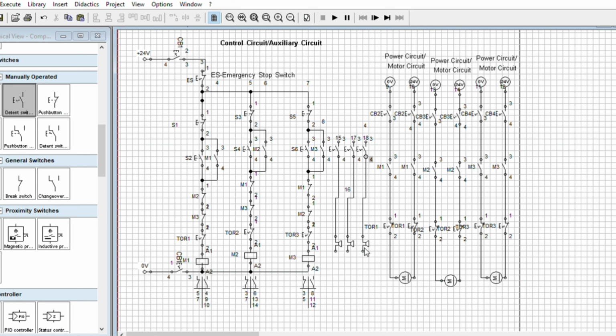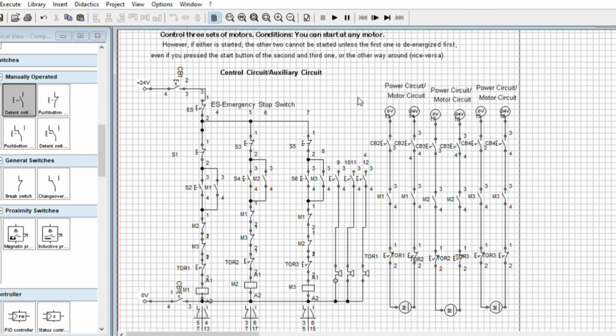Okay, and the buzzer here, or the alarm here, is not similar to the fire alarm. Otherwise the inhabitants, the people inside the building, might go out and mistakenly decide that it is a fire alarm. It's not a horn for fire alarm, but only for the area buzzer. Only the people inside the operating area or the industrial area where the motor is in operation. So TOR1. Do not use a big buzzer or fire alarm horn.